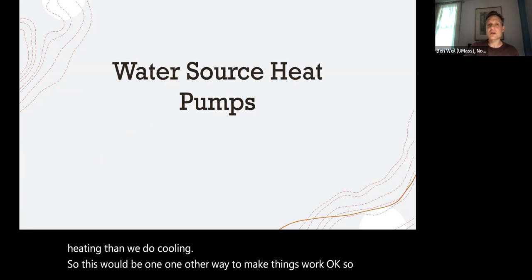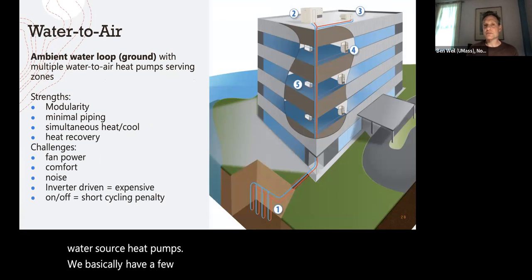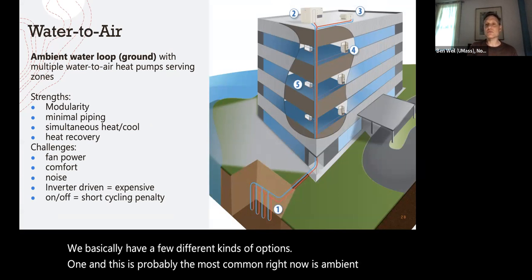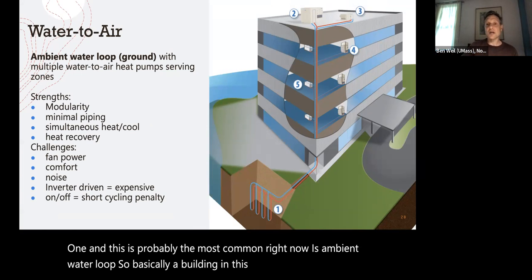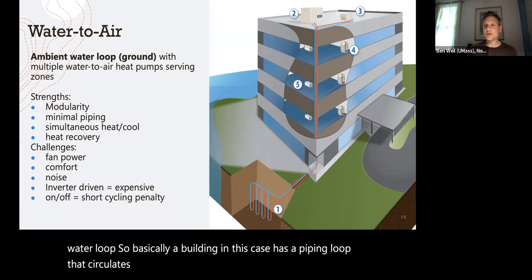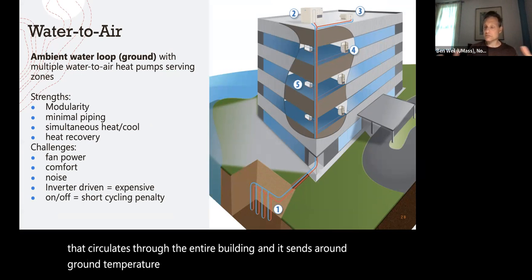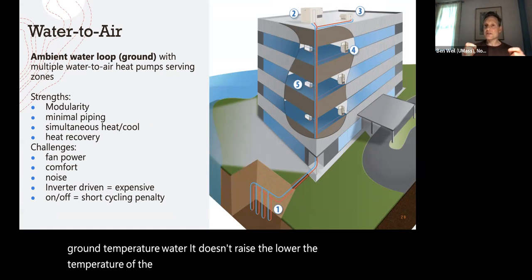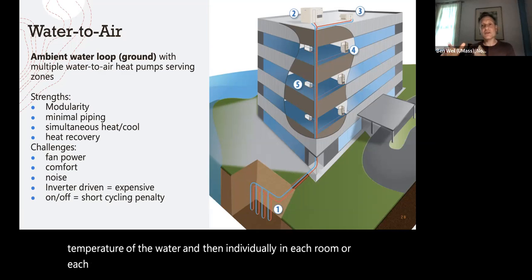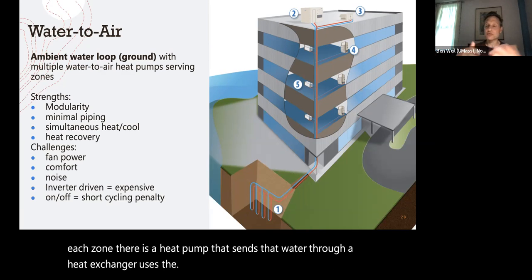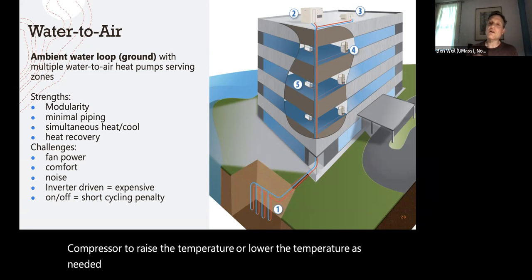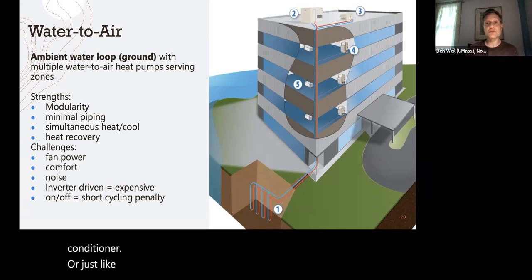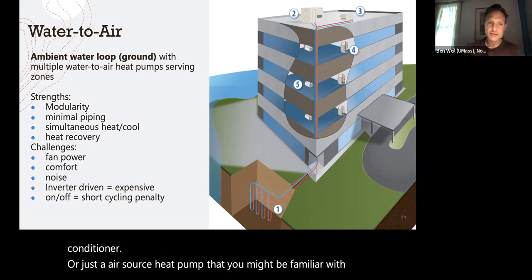Okay, so water source heat pumps. We basically have a few different kinds of options. One, and this is probably the most common right now, is ambient water loop. So basically a building, in this case, has a piping loop that circulates through the entire building, and it sends around ground temperature water. It doesn't raise nor lower the temperature of the water. And then individually in each room or each zone, there is a heat pump that sends that water through a heat exchanger, uses the compressor to raise the temperature or lower the temperature as needed, and then blows air over the refrigerant, just like an air conditioner, or just like an air source heat pump that you might be familiar with if you've got a mini split or something like that.